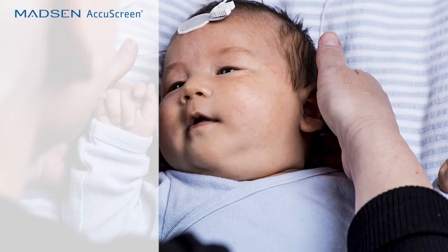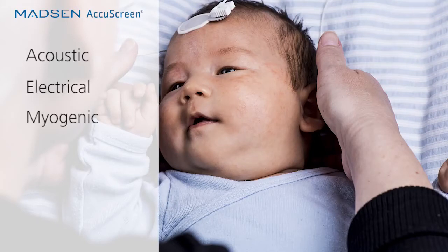Noise is a common problem when working with hearing screening. In the world of hearing screening, there are three major noise types: acoustic noise, electrical noise, and myogenic noise. Acoustic noise is basically unwanted background sounds such as crying babies, chatter, ventilation noise, or beeping or buzzing equipment. Electrical noise may stem from, for example, cell phones, electrical equipment such as TV monitors, or fluorescent tubes. Myogenic noise is actually a special case of electrical noise that originates from muscle tension.